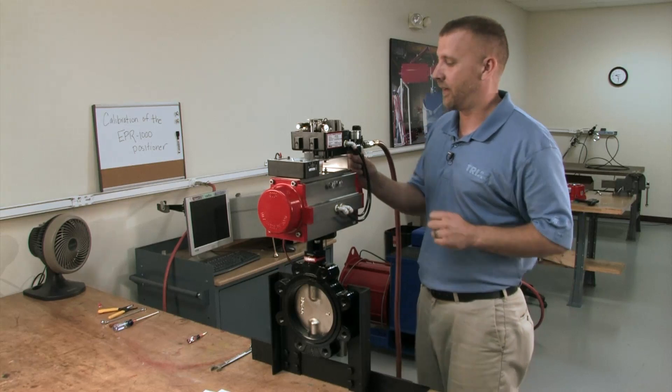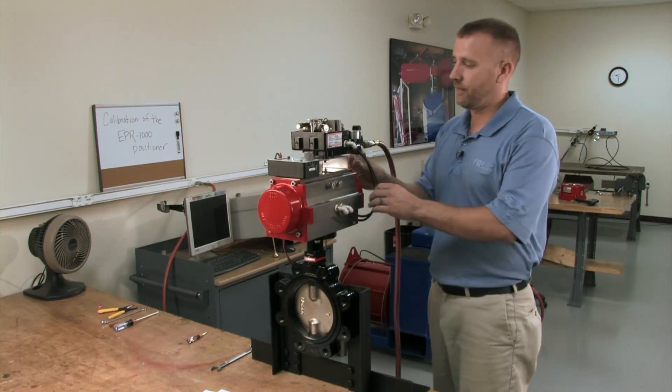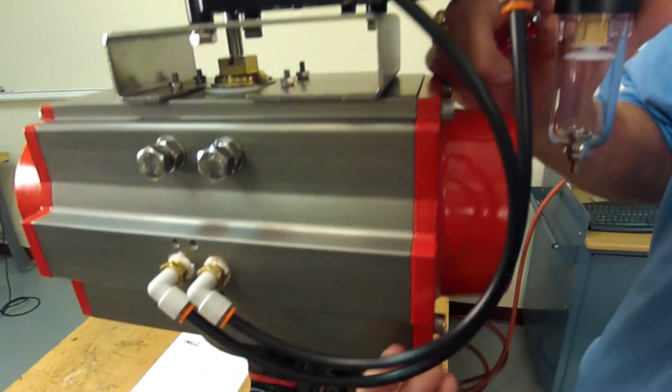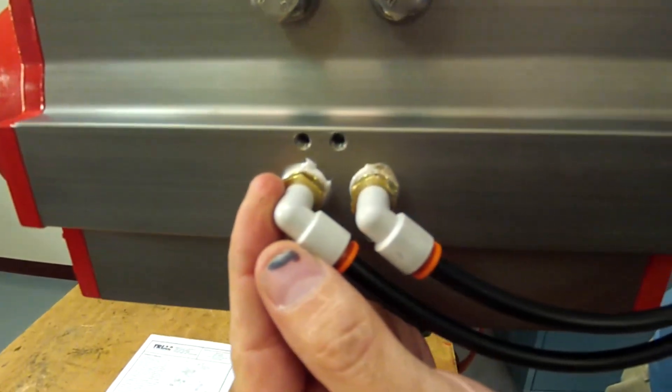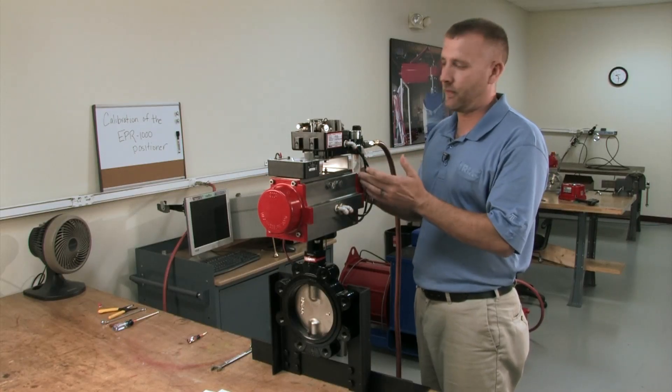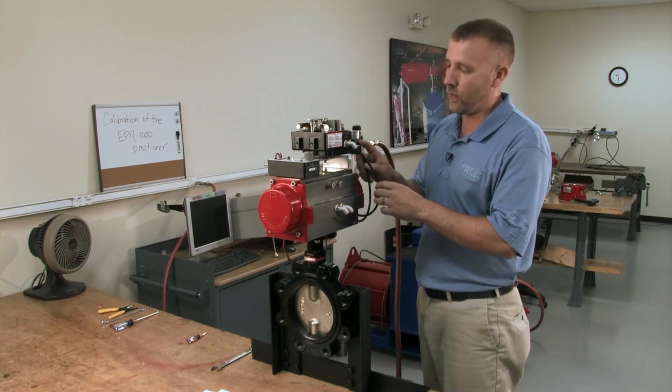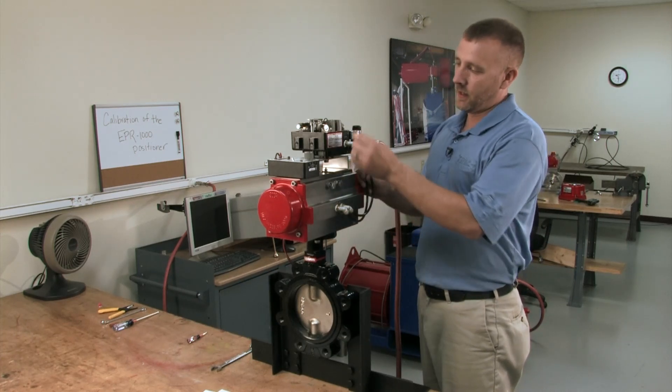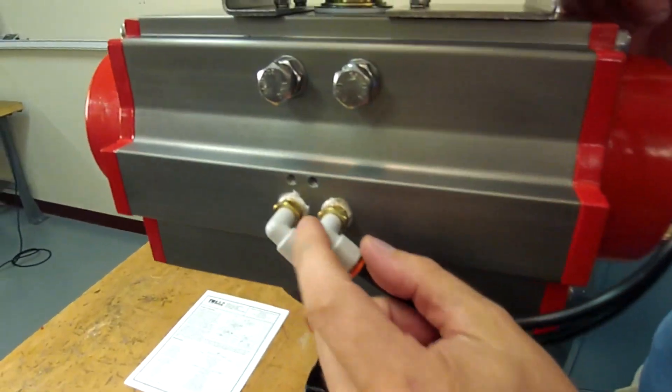Just one more thing I'd like to explain is your tubing on your actuator. Your OUT1 port goes to your counterclockwise drive port on your actuator. That would be for single acting. Like I said, we tube it up for double acting. So, your OUT1 goes to your counterclockwise and your OUT2 goes to your clockwise port.